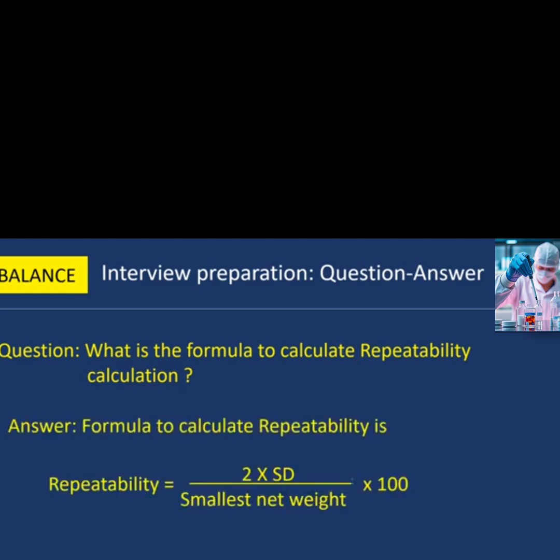Next question: what is the formula to calculate repeatability? The formula to calculate repeatability is: Repeatability = (2 × SD) ÷ Smallest Net Weight × 100, where SD is standard deviation.